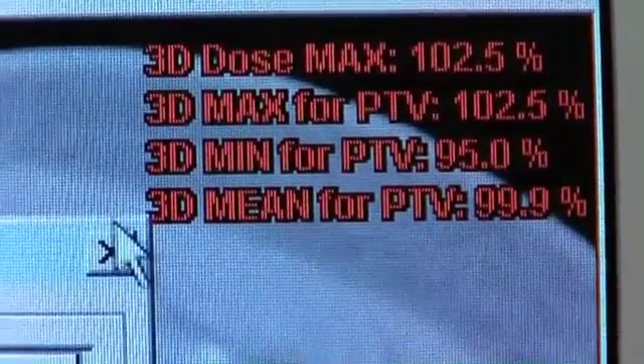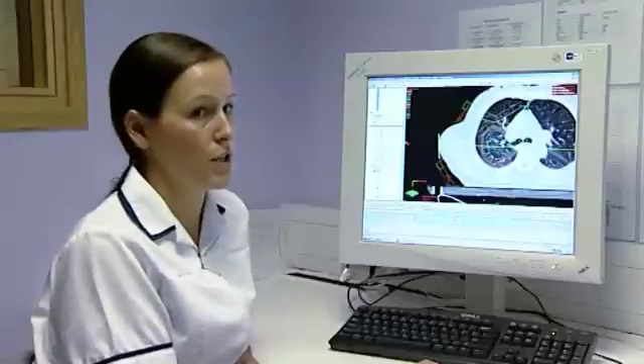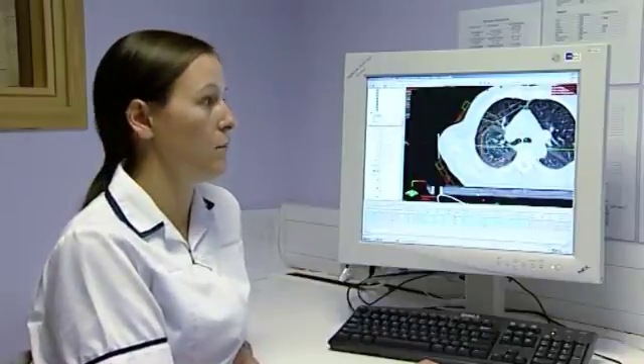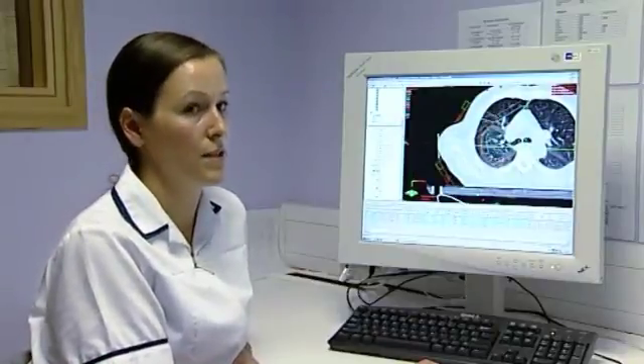All these percentages are within the ICRU recommendations, which state that the maximum dose must be no more than 107% and the minimum dose must be no less than 95%.